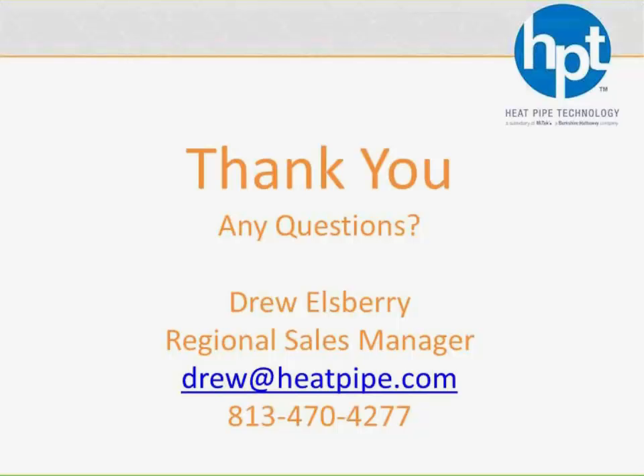So first question, how reliable are those solenoid valves? How long do they typically last? Manufacturer, warranty, all that good stuff. Okay, so they are very reliable. We don't make solenoid valves. We get them from Sporlan. So it's a very common valve. I'm not going to say that they last forever, but they last a lot longer than the air handler does. The life of a solenoid valve is based on how often it opens and closes. Even if we're shutting down circuits at those peak days, it doesn't happen a whole lot. So the amount of times the solenoid valves are open and closed each year is very seldom. So they're going to last a long time.